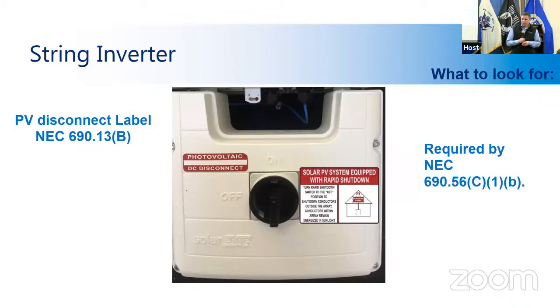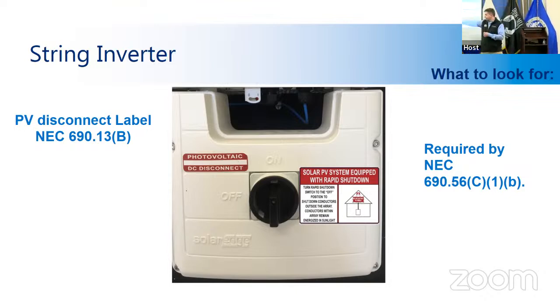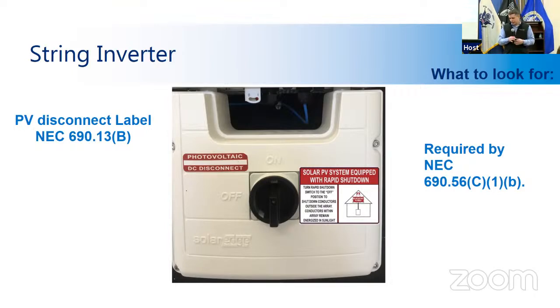All right, some more on the inverters. Now we're going to look at the labeling requirements for the inverter. This one in this picture has a disconnect handle built right into the inverter, so you can just shut the system down right there. It has to be labeled as the DC PV disconnect. You can see right here. And it has to have a label showing that there's rapid shutdown installed, just so if someone does have to shut down the system very quickly, they know where to go and how to do it. It's very important so that you can have a safe condition.